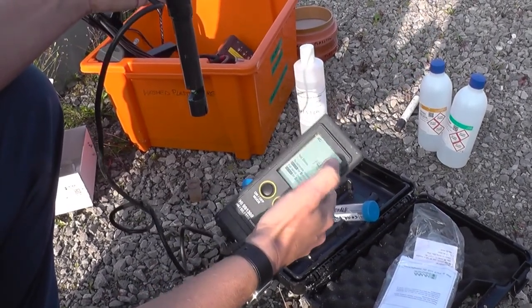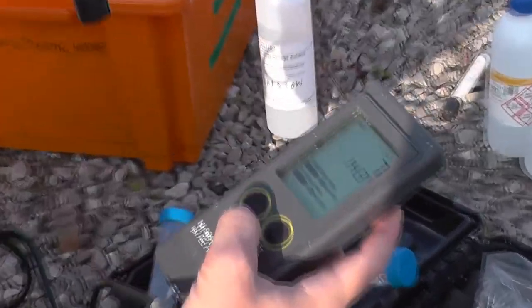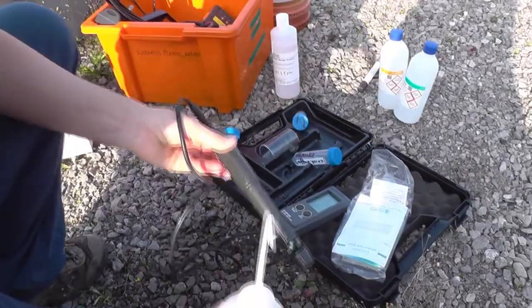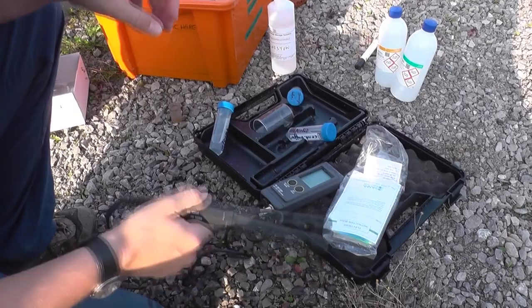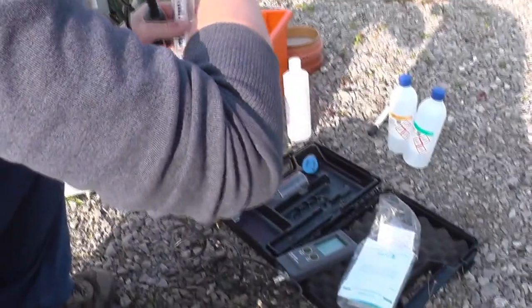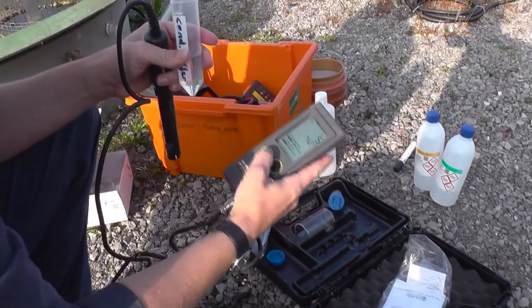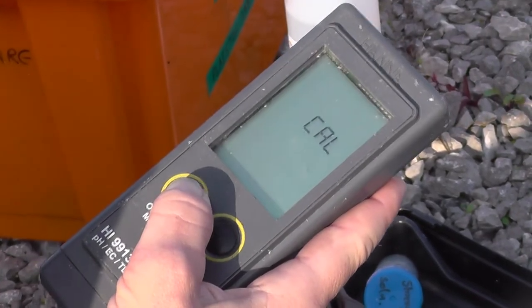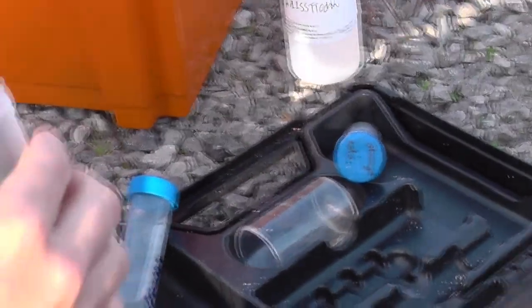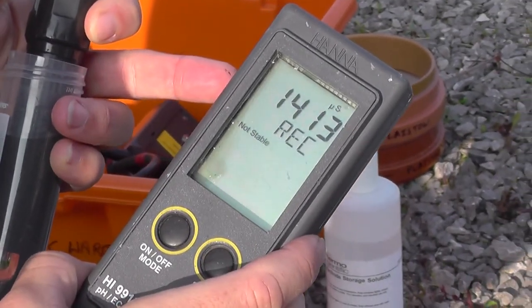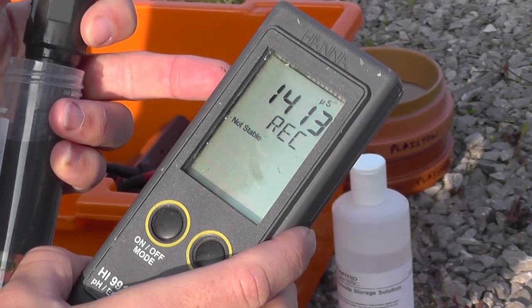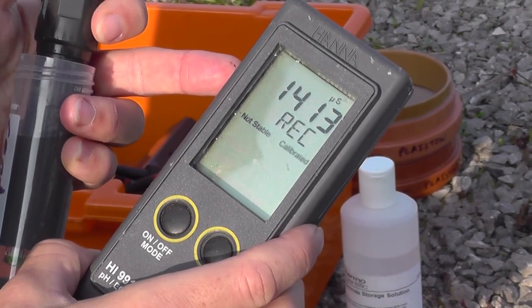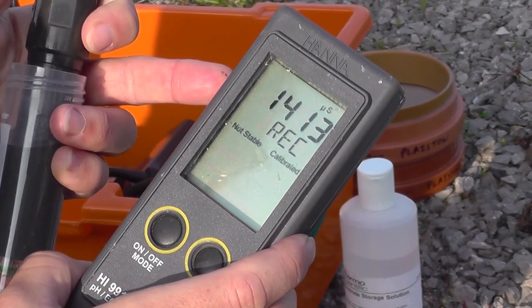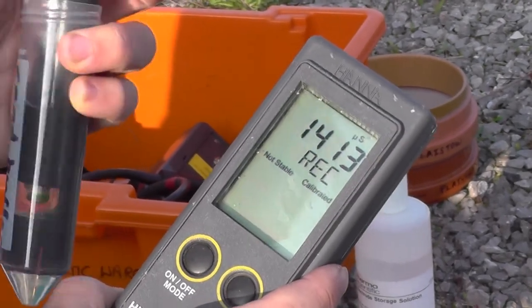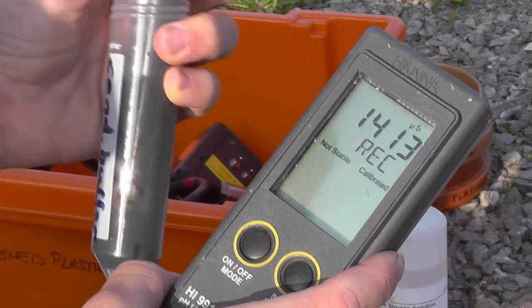So that's conductivity in microsiemens up here. So now we can calibrate for the conductivity measurement. Again, briefly giving the probe a quick rinse before shaking off the excess water. Getting our conductivity buffer ready, and then getting this into calibration mode by pressing this for 3 seconds. So that's the conductivity that's expected from the calibration buffer, 1413. It's recording. Hopefully it'll stabilize. Yeah. Try shaking this around in here a little bit for any effects of the water that was on the probe.